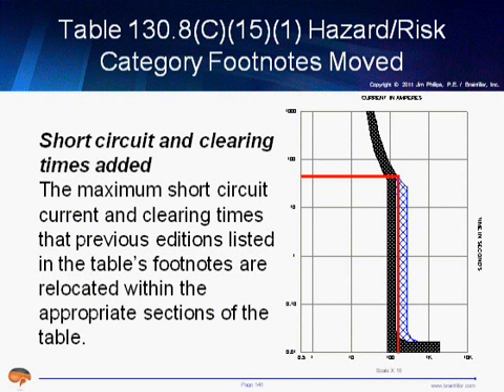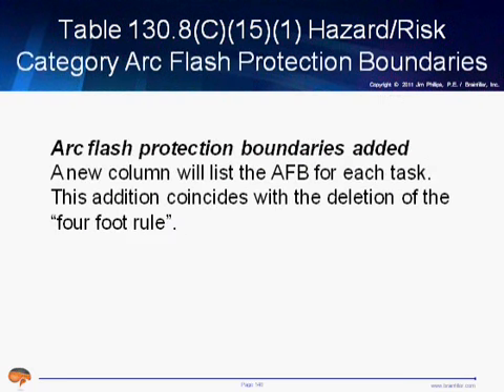I don't know. I kind of doubt it. Bus bars burn up. Sometimes arcs extinguish, but you have no way of knowing. There is something known as the 2-second rule from IEEE, where depending on whether or not you have sufficient room to escape and other factors, you may be able to cut this off at 2 seconds, assuming that someone has jumped out of the way or, I guess, worst case, blown out of the way.